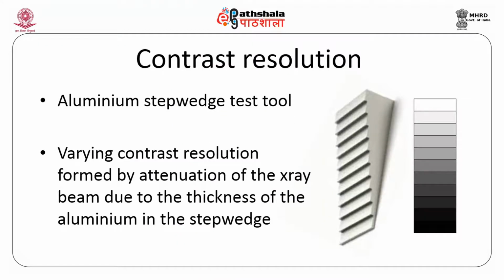In some cases, if I want to have good contrast resolution, how do I check this contrast resolution? From an X-ray imaging modality, the best method is using an aluminum step wedge. If you want to do quality assurance for a CR machine to see whether your contrast resolution is good, one can use this aluminum step wedge to have the pattern which is the contrast resolution. Varying contrast formed by attenuation of the X-ray beam due to the thickness of the aluminum in the step wedge creates this image of grayscale.